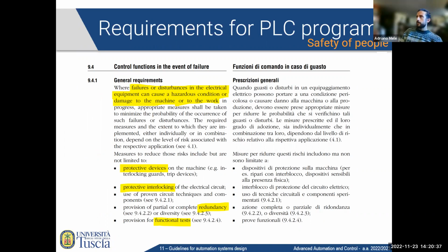Okay, next, this is the paragraph 9.4, which we were citing before. So general requirements for the control functions in the event of failure. So this paragraph is about what happens if my plant has a failure and what should my controllers do in that case. So general requirements. When failures or disturbances in the electrical equipment can cause a hazardous condition or damage to the machine or to the work in progress, appropriate measures shall be taken to minimize the probability of the occurrence of such failures or disturbances. The required measures and the extent to which they are implemented, either individually or in combination, depend on the level of risk associated with the respective application. So, again, of course, appropriate measures should be put into action to minimize that any failure or disturbance happen. That's trivial, let's say.